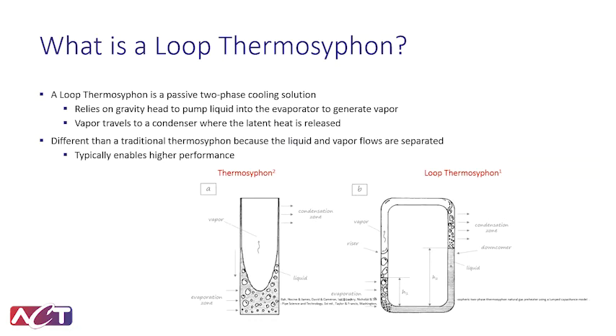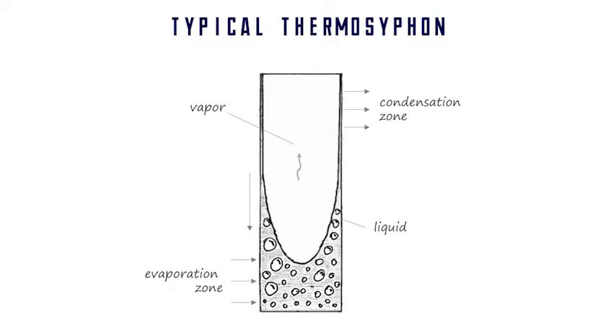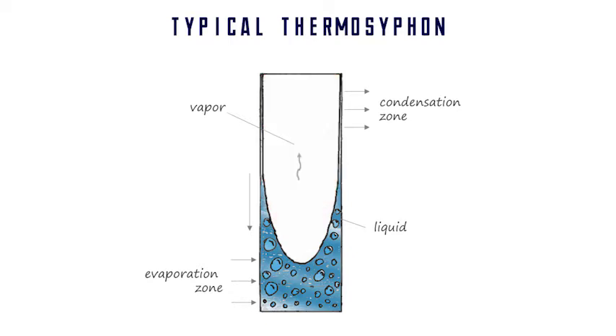A loop thermosiphon is a passive two-phase cooling device. It relies on gravity head to drive the liquid around the loop. You may be familiar with typical thermosiphons as shown here on the left. A typical thermosiphon has a pool of liquid on the bottom. You add heat to it, it evaporates the liquid, and the vapor naturally rises to the top of the pipe. When you remove that heat from the top of the pipe, the vapor condenses into liquid and falls back down by gravity. The liquid and vapor operate in the same space inside of the pipe.